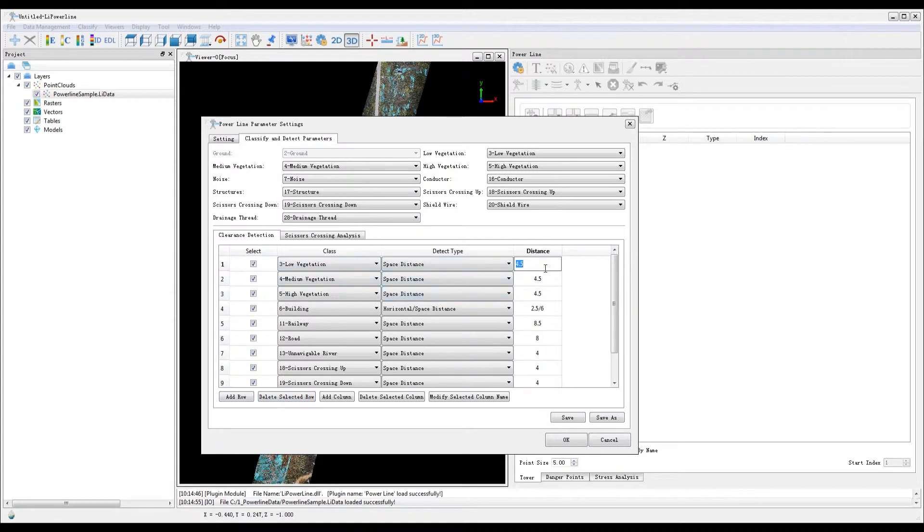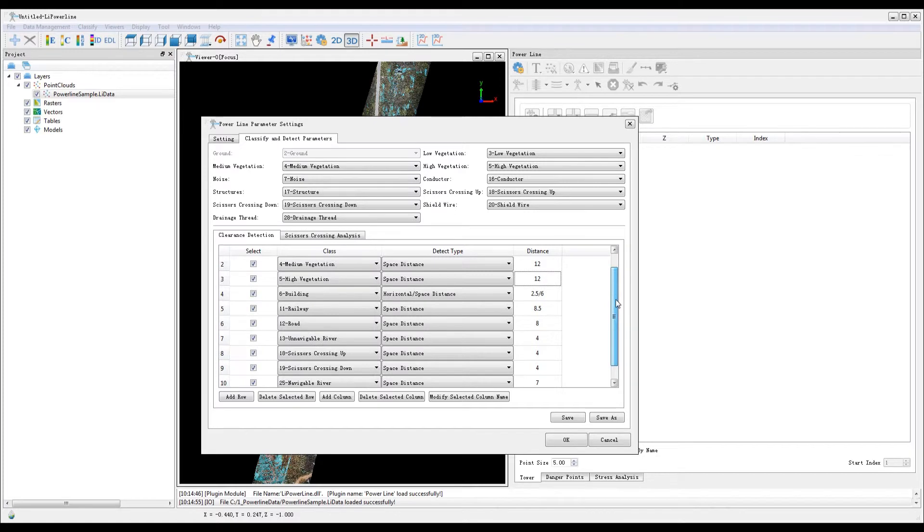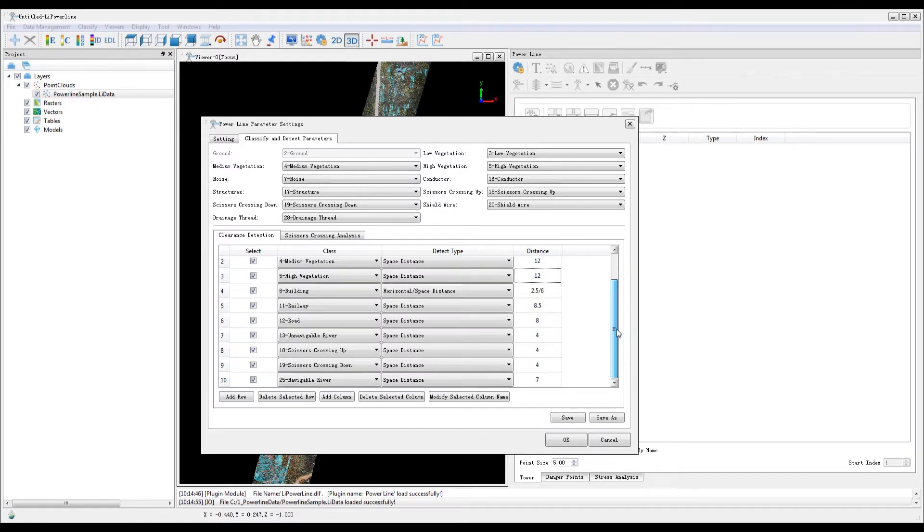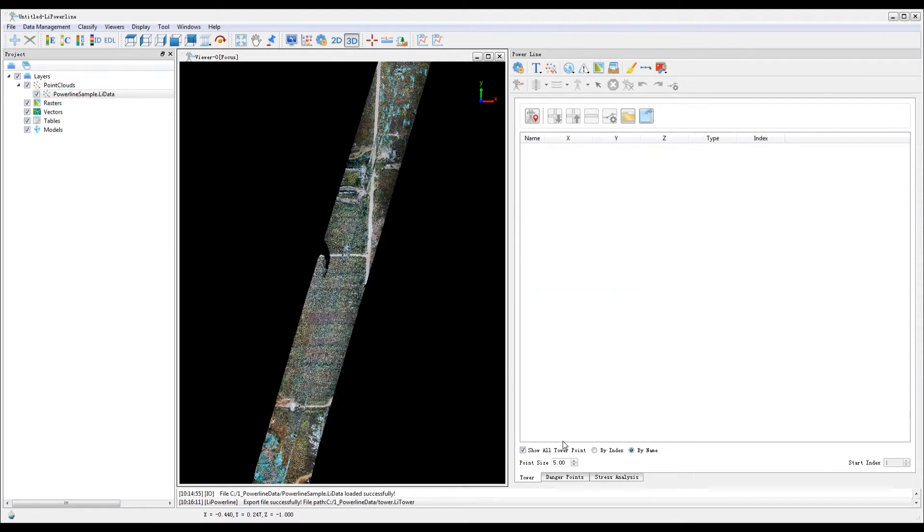You can change the detection distance for class 3 low vegetation, class 4 medium vegetation, and class 5 high vegetation to 12 meters. This means that vegetation within 12 meters of the powerline violates the clearance distance.